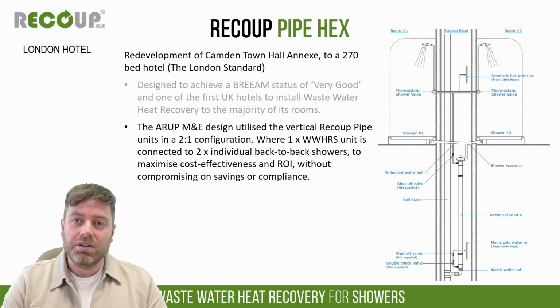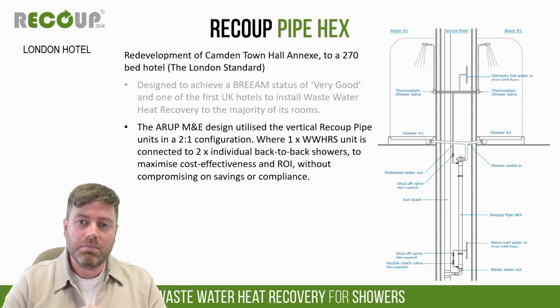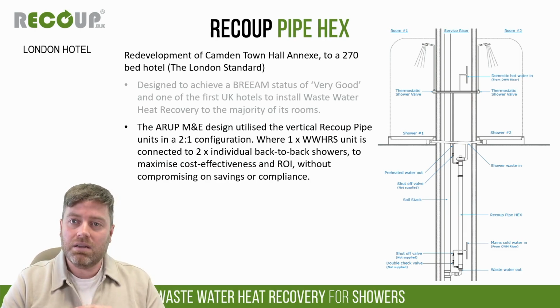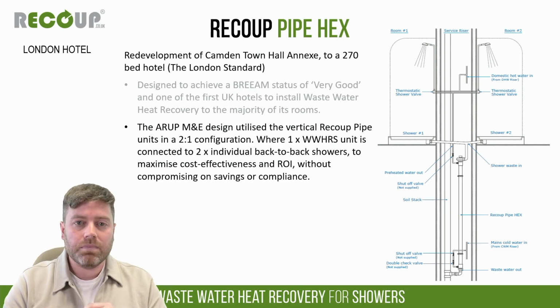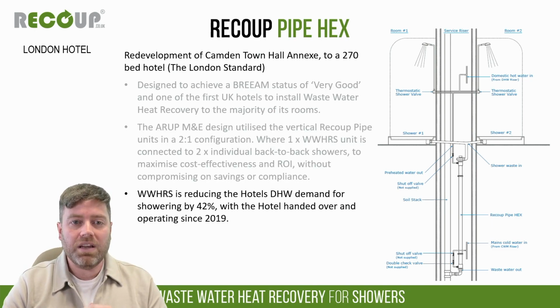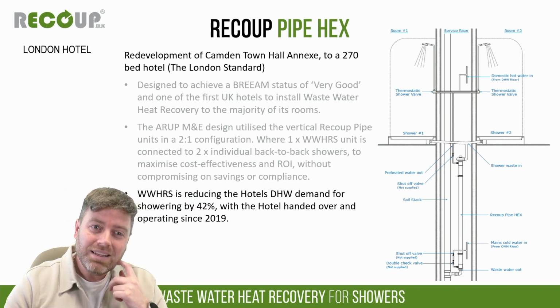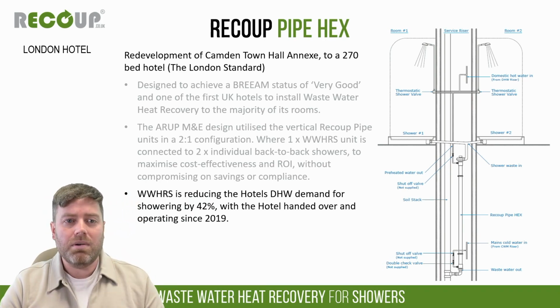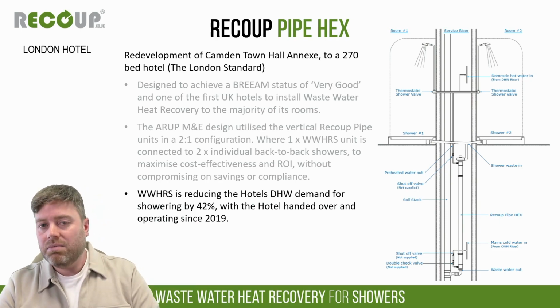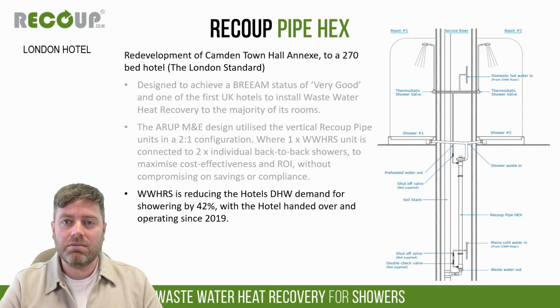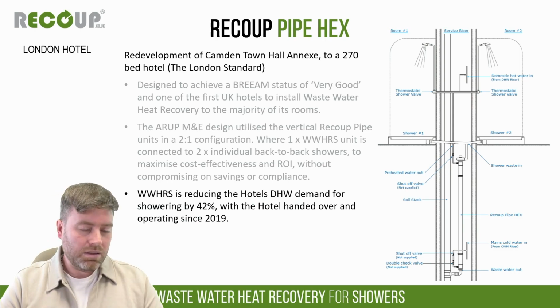So if you can get 2 showers into one like this, anywhere you've got service risers, it's a really, really good way to integrate it, and it's kind of become a bit of a blueprint for how we see wastewater heat recovery being built into hotels and that kind of thing, where you've got these service risers that lend themselves to it. That's been installed since about 2019, and domestic hot water demand for the showering has been reduced by about 42% in this case. So yeah, it's really quite a significant impact when you think of the amount of hot water used for showering in hotels.